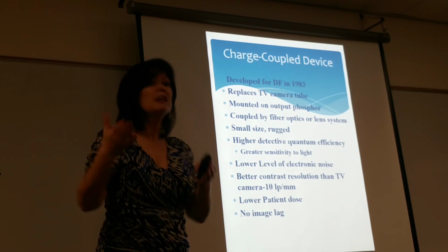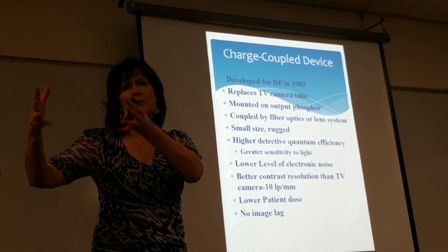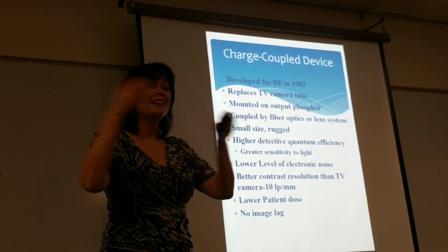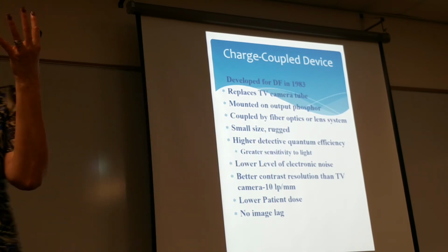That helps, right? But then when you drag the fluoroscope from one body part to the other, it takes a little while for the image to come up. I'm talking seconds, but still, that's what we mean by image lag. With the CCD, we don't have that. So again, what does that do? Lower patient dose. It says no maintenance, and look here, no pincushion effect. That's not something that we have to worry about when we have digital fluorography. Lots of good things with that.